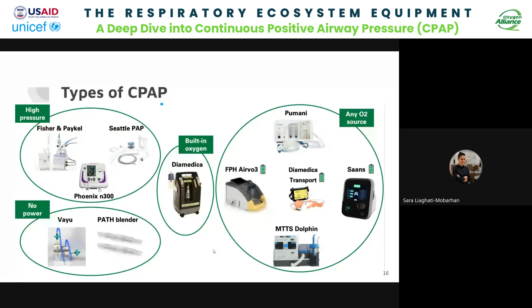So as I said before, the type of oxygen that you select, very important. In many hospitals in Malawi, there's no high pressured air. So if you need to have high pressured medical air, then maybe those products are not appropriate for your hospital. So it's important to consider all of these different infrastructural elements, and we'll go back to that a little bit later in the presentation. But as you can see here, these are many different models of CPAPs, but they all work fundamentally in the same way. There's a pressure driver, there's a pressure regulator, there's a patient circuit, and there's the option for humidification. Next slide. I'll hand over to Brittany and Tama for the implementation of CPAP in Ghana.